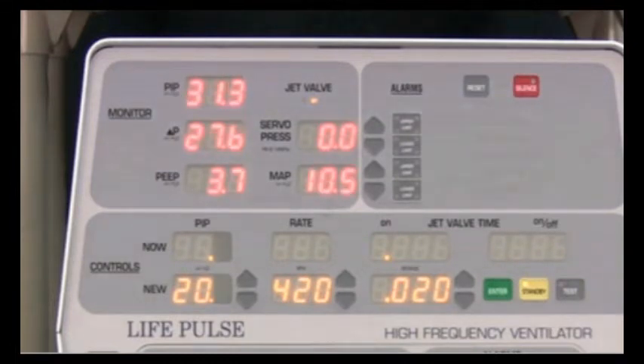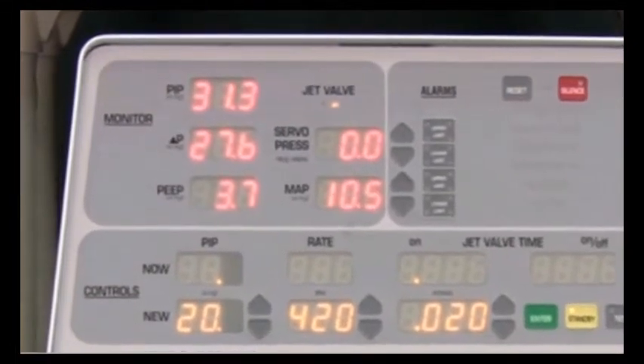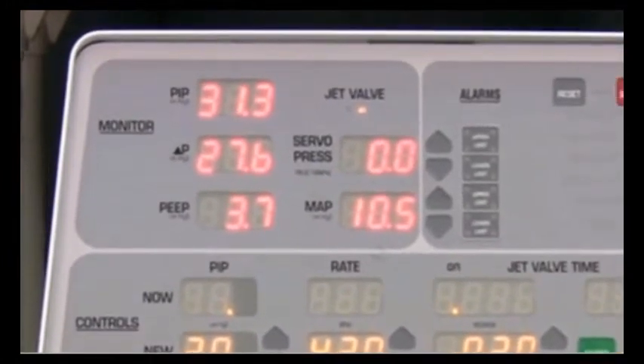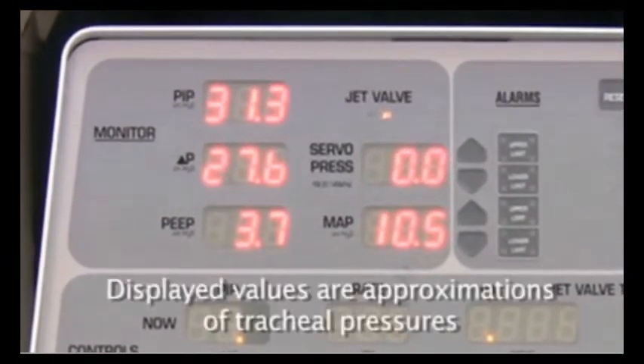In the standby mode, the LifePulse monitors and displays the airway pressures as if they are measured at the distal tip of the ET tube. The LifePulse approximates distal tip values. So the numbers you see displayed in the LifePulse's monitoring section will be approximations of distal tip values. These pressures might be slightly different from the pressures displayed on the patient's current ventilator. That's okay. Just remember that the information is coming from two different places.